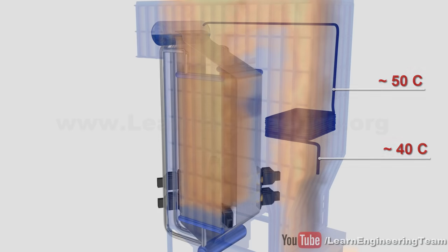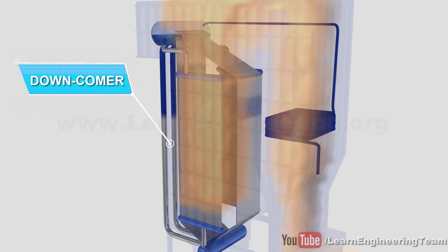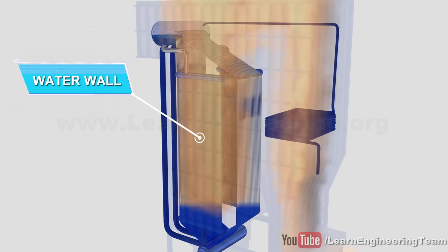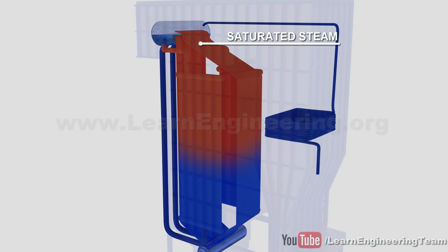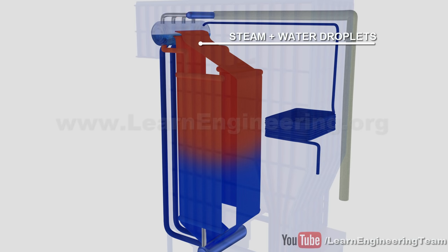From there, the water flows into a steam drum to the downcomer. It then passes through a narrow tube section called a water wall. The phase change of the water happens in the water wall. The steam that is produced, in addition to some water droplets, enters the steam drum again.